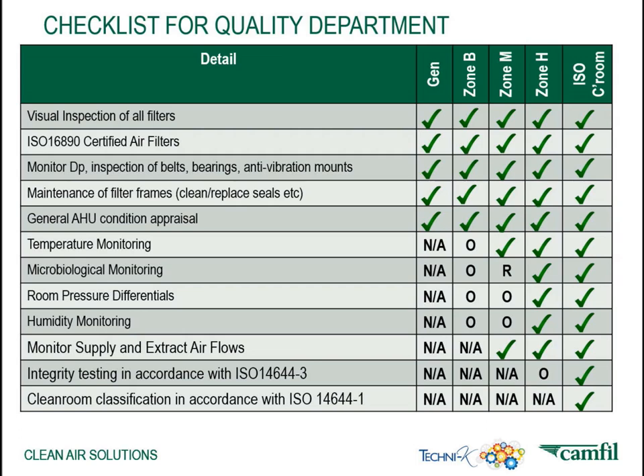This checklist is a guide that can be used to inspect the air handling units for different areas based on requirements for the areas. Notice all the areas have basic requirements of ensuring the air filters are certified to their standards. All belts, bearings, and anti-vibration mounts are monitored and maintained, as well as ensuring no bypass is created within the air handling unit. In higher quality zones, other checks are needed, such as humidity monitoring, temperature monitoring, and microbiological monitoring. And as you can see, we have separated out in the attached checklist the requirements within each area.